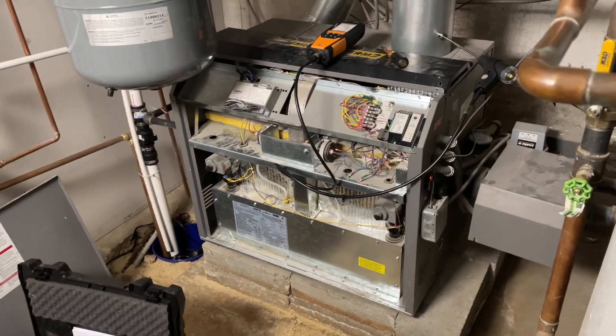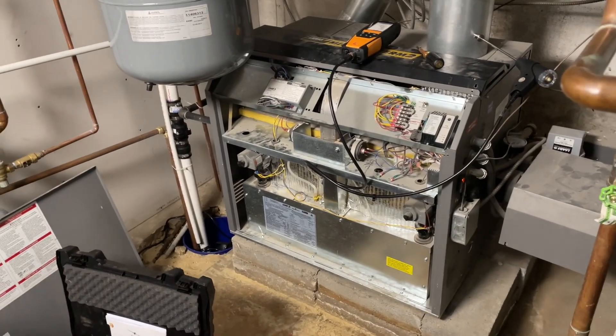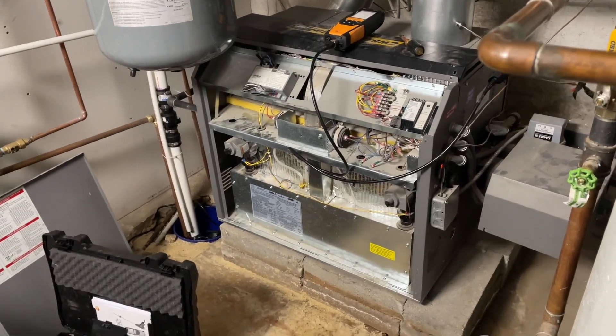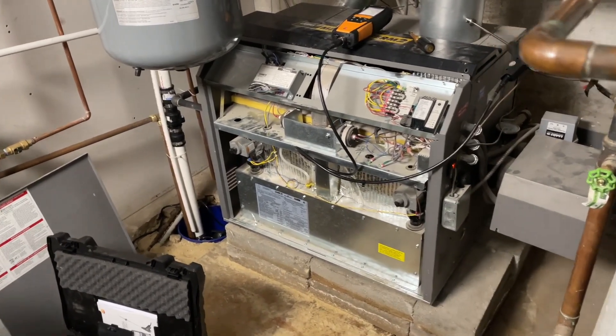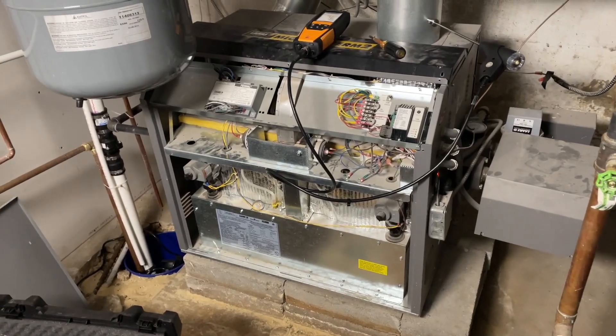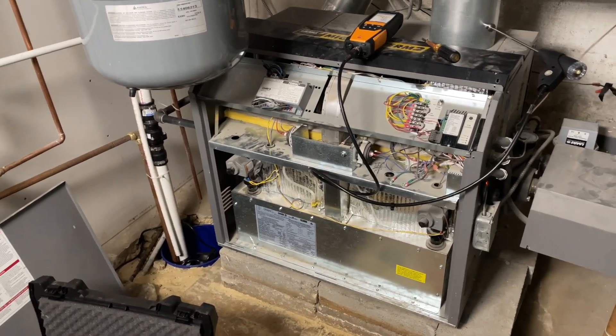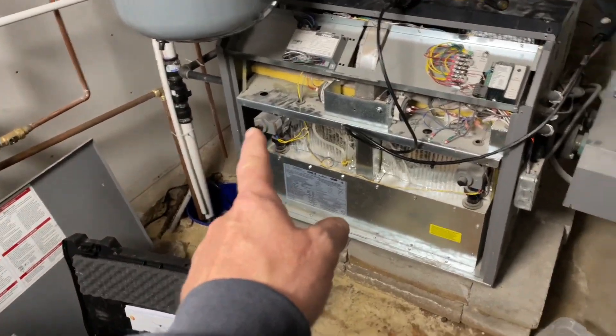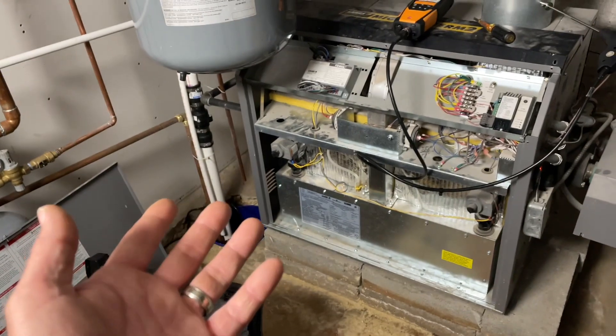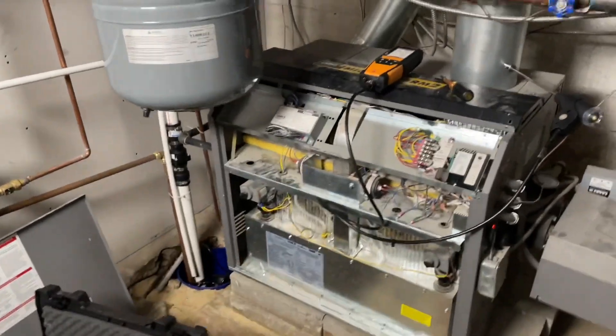A technician will be able to figure it out. When I was here last week, we had low pressure. We verified how much pressure was going into each gas valve and it was low. When this thing fired up it was choking, and I told the property agent I'm going to take you on a little walk, a little tour.